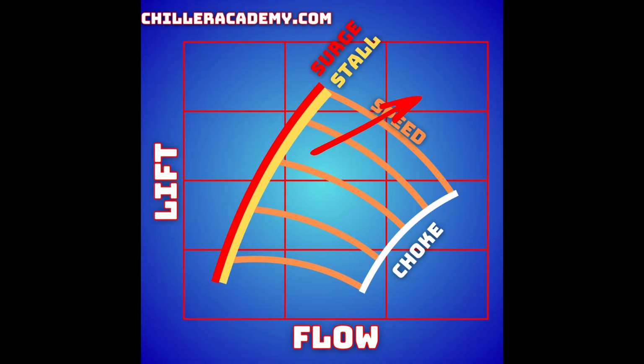But we have the opposite scenario where, if we have a high load, meaning flow, this term flow is directly connected to how much load we have. The more heat we're trying to process, the more flow we're going to have through the compressor. Okay? So just understand that. Your flow is directly tied to your load. So if we have a high load, but then we drop that lift, then we get into our choke, which can mimic, or shows similar symptoms to, a surge. Now, it's very easy to get mixed up with the terms here.